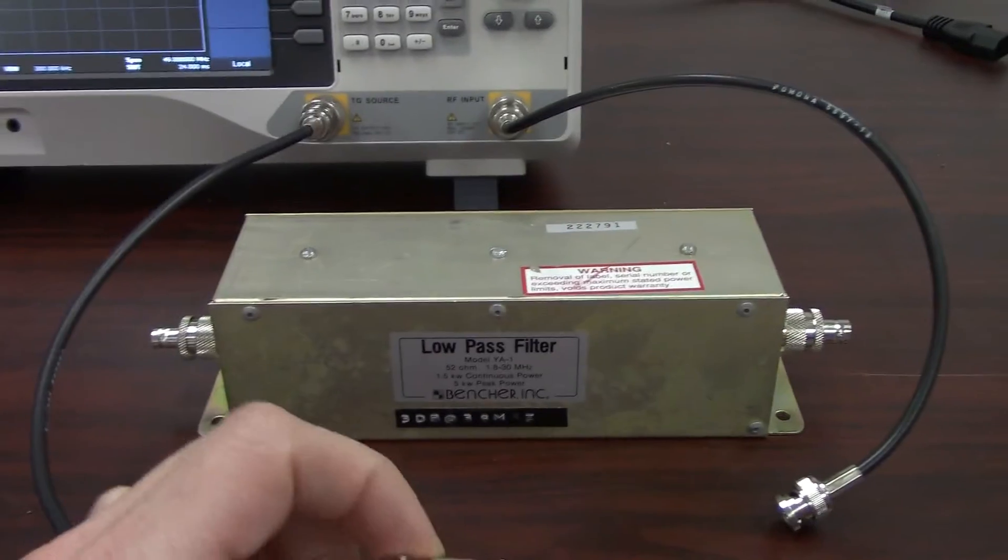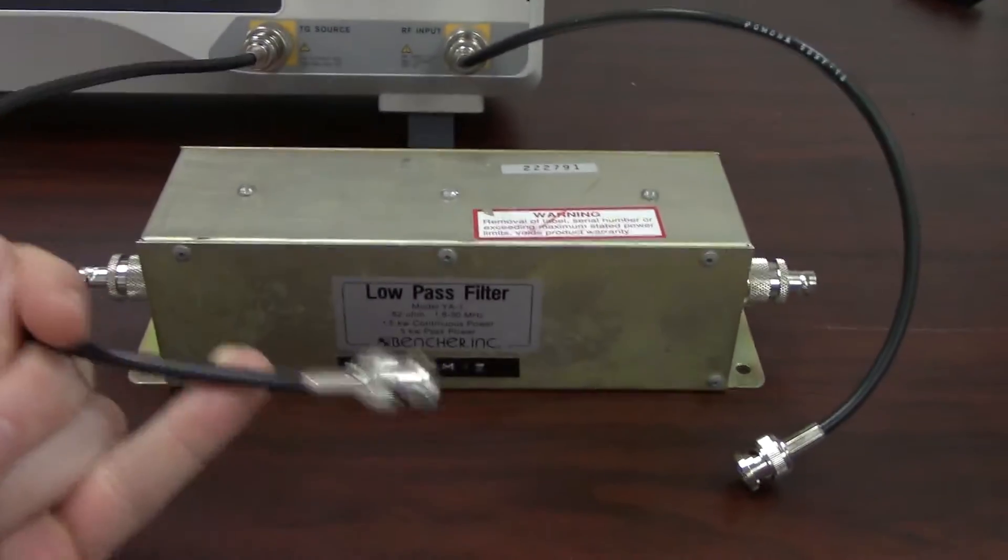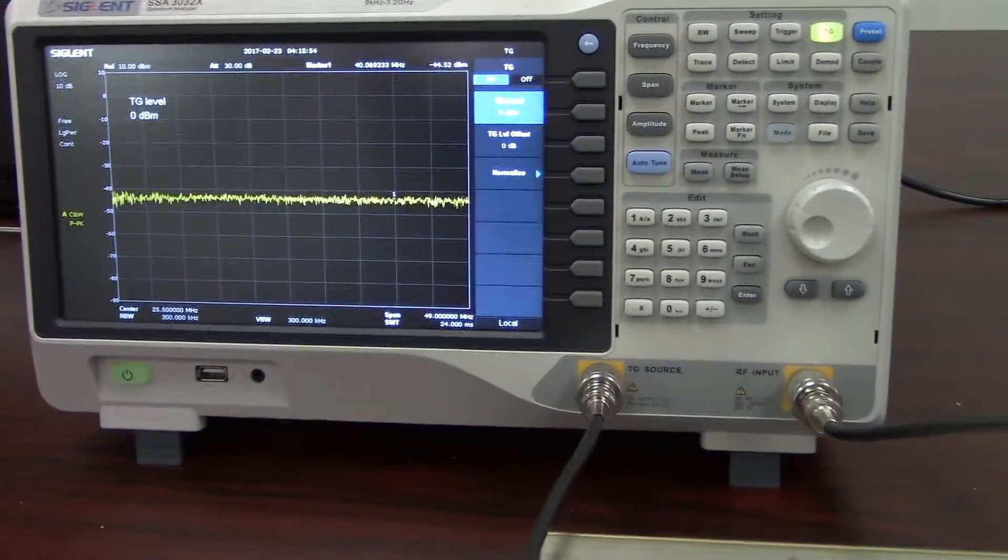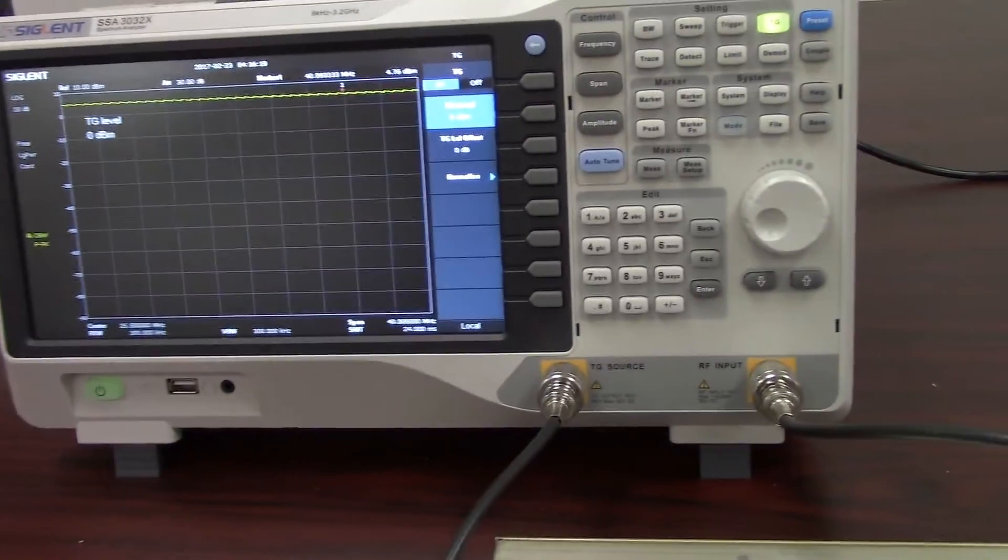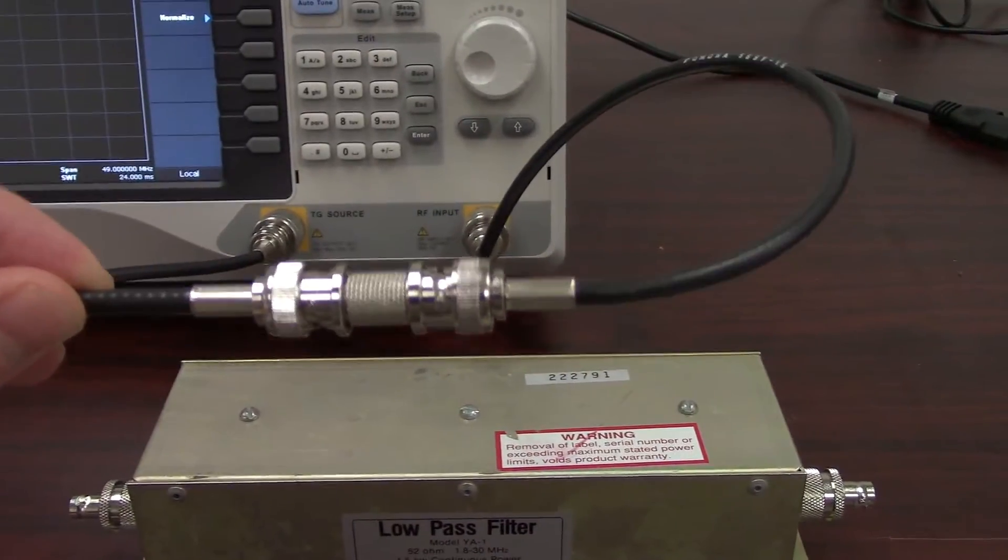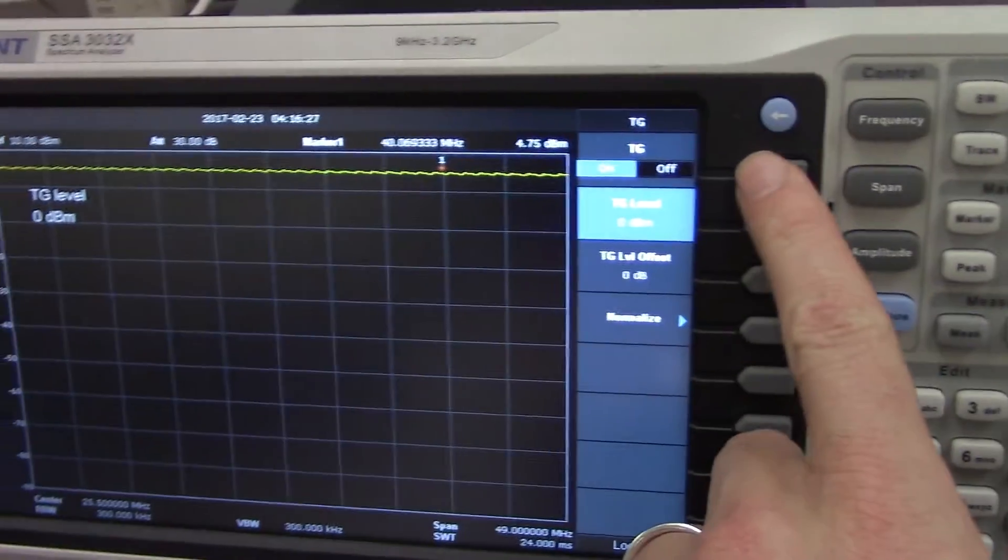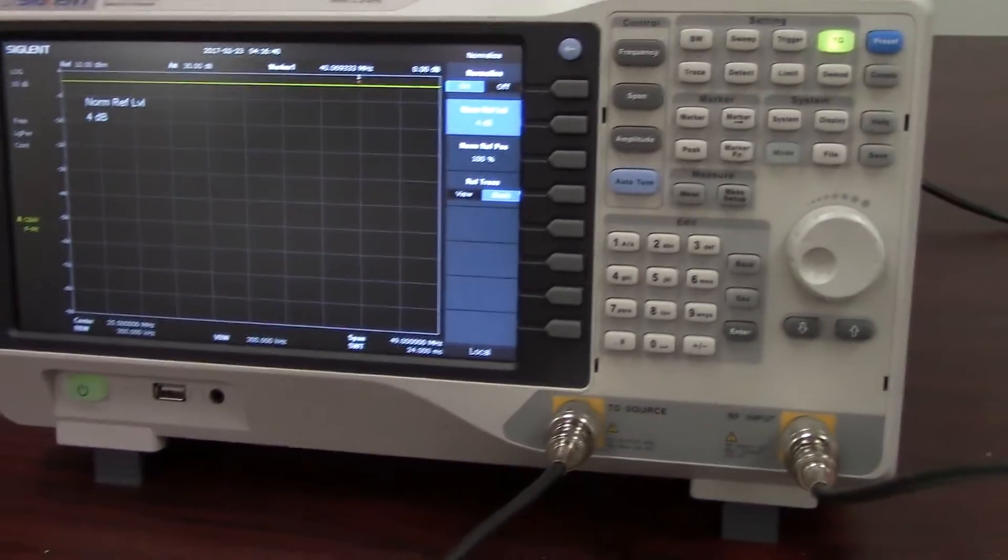The BNC barrel, we're going to be able to calibrate. So, normalizing, we're going to be able to remove the reflection and absorption effects of the cabling by doing the normalization process. Just one second, I'm going to put this barrel in and be right back. Okay, now we're back. I have put the barrel adapter in and now I'm going to turn on the tracking generator. So we've got the tracking generator on. And now I'm going to press normalize and turn the normalize trace on. And now you'll see that the line has gone flat and we are at 0 dB.